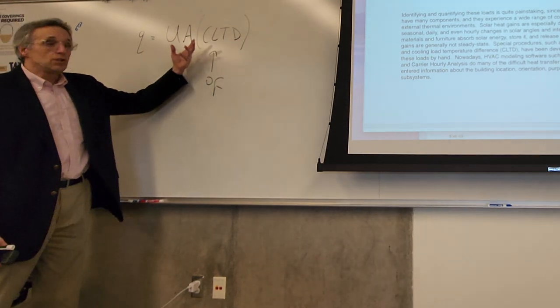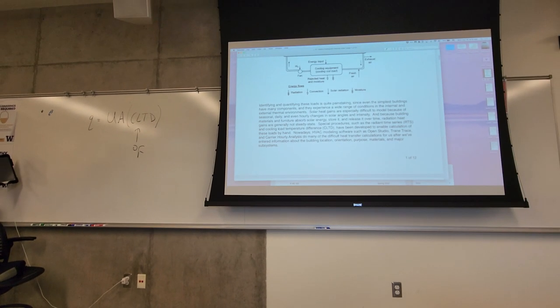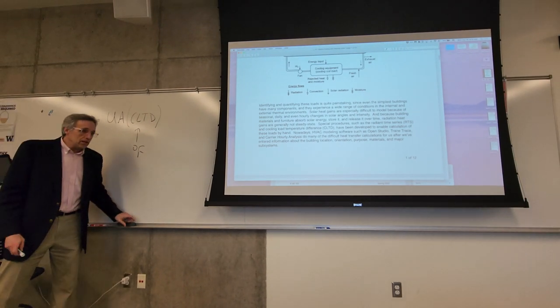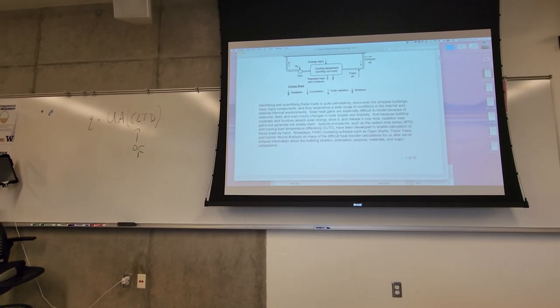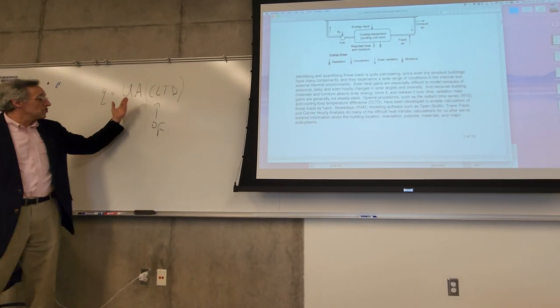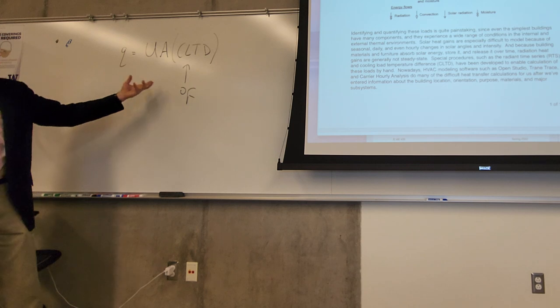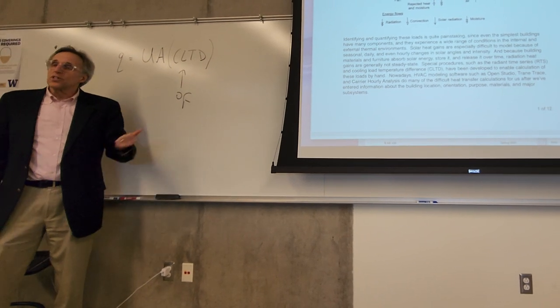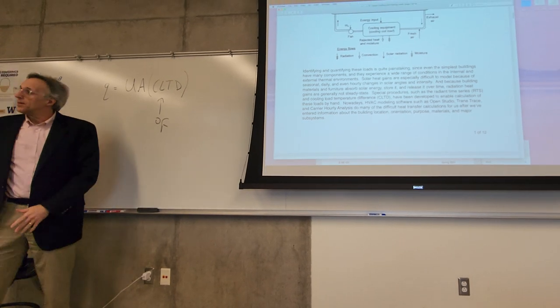When you use the CLTD method, you have to do it for every hour of the day, and for every component — each wall faces a different direction, so each will have a different CLTD. The roof has a different one too. So it's a very simple calculation but you have to do an enormous number of them. That's where spreadsheets are helpful — you can set this up in a spreadsheet and it becomes quite simple.